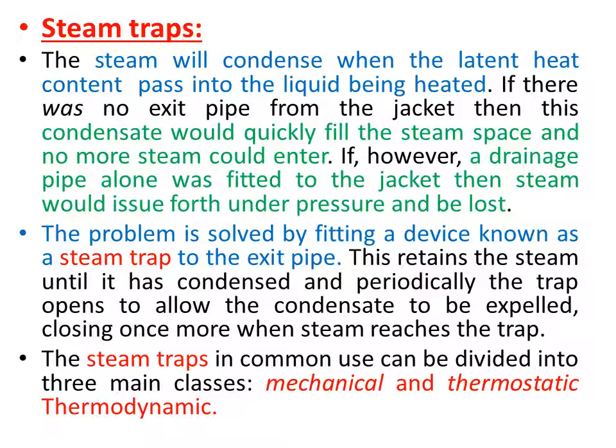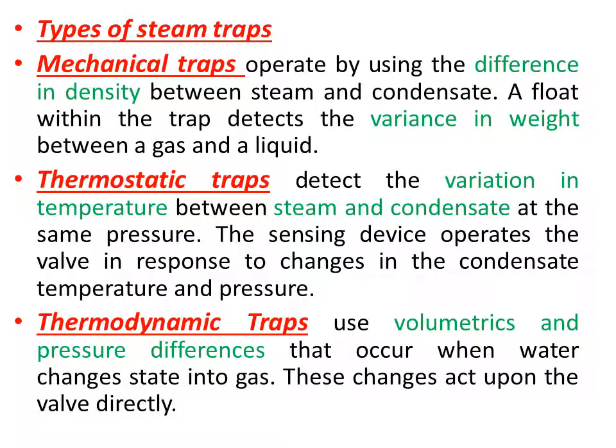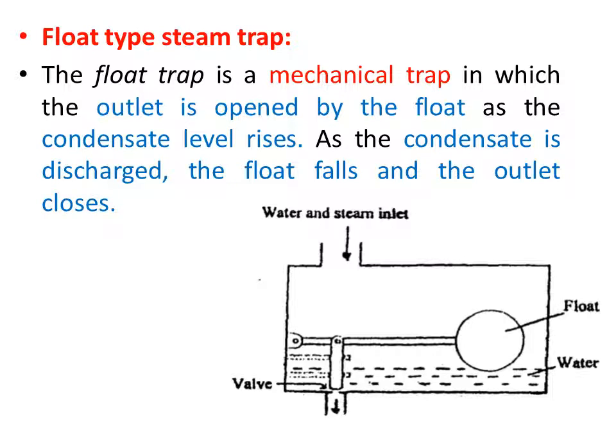The steam trap closes once more when steam reaches the trap. The steam trap has three types: mechanical, thermostatic, and thermodynamic. Mechanical traps operate by using the difference in density between the steam and the condensate. Thermostatic traps detect the variation in temperature between steam and the condensate. Thermodynamic steam traps use the volumetrics and pressure differences between steam and the condensate.